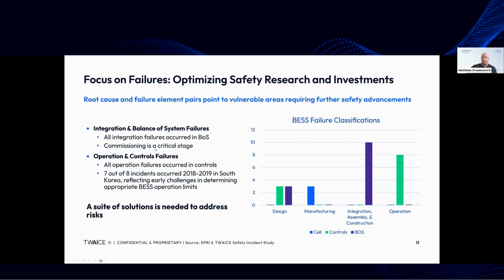I've probably shown this slide before on TWAICE webinars, but in the past we've worked with EPRI to try and quantify types of failures we see in the industry, and about 60% of failures occur in the first 2 years of operation with a BESS system. Oftentimes these failures can be root caused back to balance of systems, essentially the integration, and a lot of these are introduced during the commissioning process.